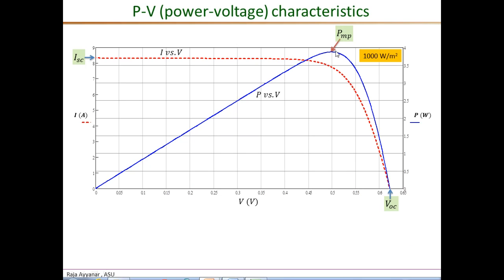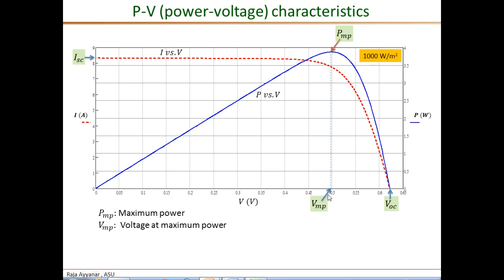The point at which maximum power occurs is called the maximum power point, and the power here is PMP — the maximum power. The voltage at which power is maximum is called the maximum power point voltage VMP, which in this example is very close to 0.5 volts. The corresponding current at this maximum power point, read from the I-V characteristic at VMP, is called the maximum power point current IMP. In this example IMP is just slightly less than 8 amperes and PMP is about 3.9 watts for a single cell.